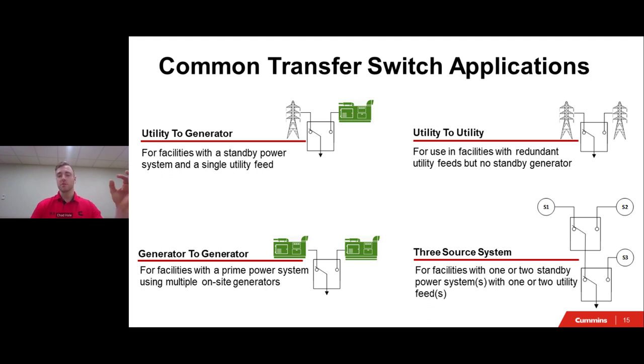So in a system, you would typically see the emergency power source being the generator, and then the utility being the normal, and the ATS transferring between the two. Next up, you have gen-to-gen. This application type is most notably seen in prime power applications.